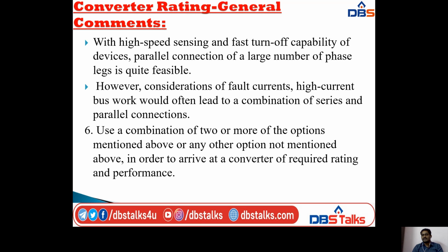However, considerations of fault currents and high current bus work would often lead to a combination of series and parallel connections. Actually we took series connection as separate and parallel connection as separate, but considering fault currents, high current bus work would often lead to a combination of both series and parallel. And coming to the last point, use a combination of 2 or more of the options.